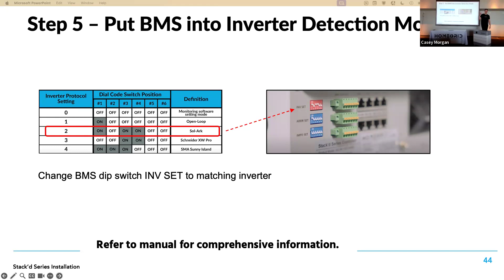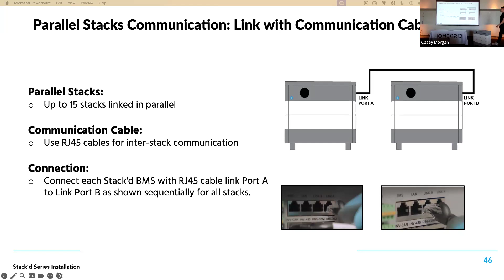I do want to just touch on parallel installs. How do we do that? I know you guys won't remember this, but just to give you an idea of how this works: you're going to connect each module, or each BMS, to each other with a comms cable. This comes included with each BMS — we include an extra comms cable, about 6 feet long. You're going to connect the comms cable from link A to link B, to link A to link B, and so on. Once that's done, go to the next slide.